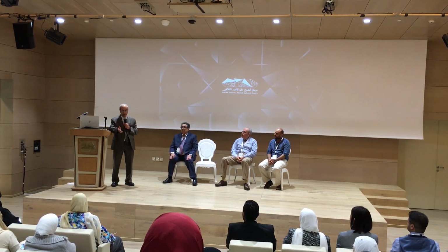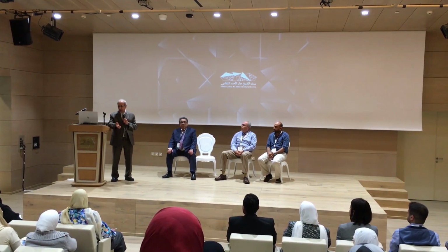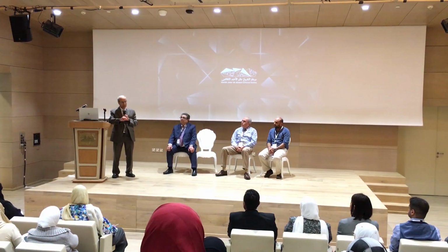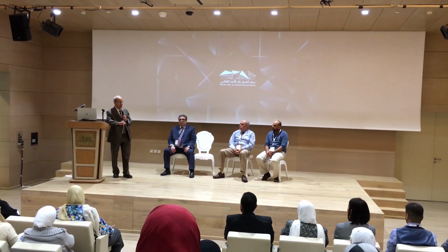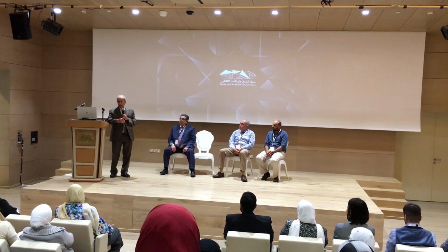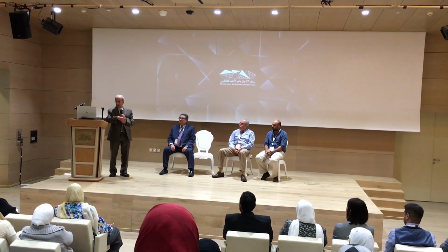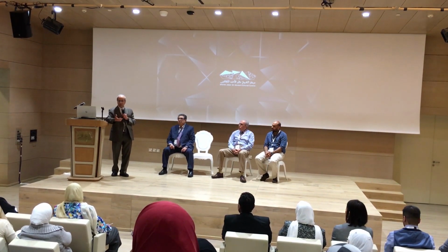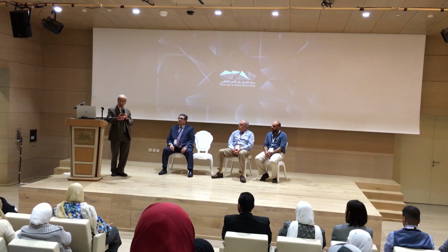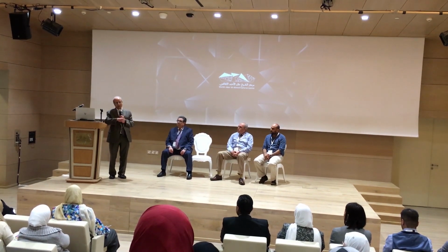And in the United States, inspections are unannounced. We don't tell you when we're coming. You have a 3-month window, you know that window, but you don't know when exactly. So in that case, the team may drop in any time during those 3 months. Outside the United States, well, it's different because we have to travel and it involves a lot of logistics. So usually we pre-arrange a date. I call the lab director and we agree on a mutually acceptable date.